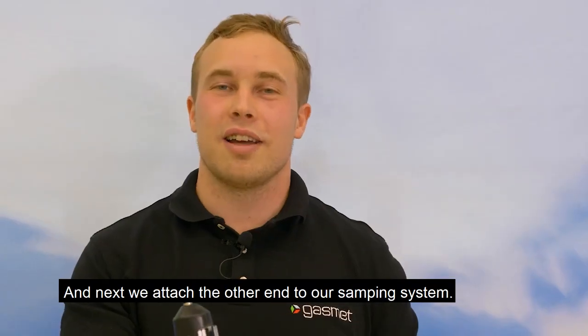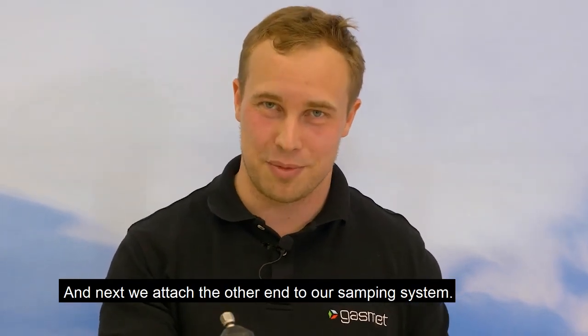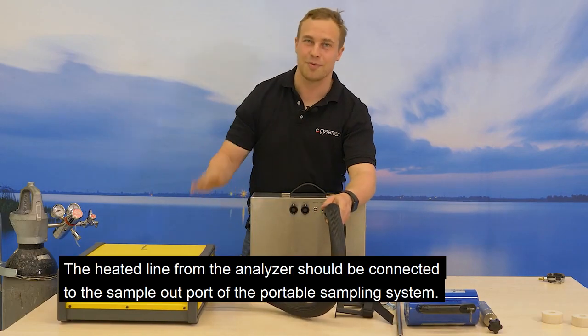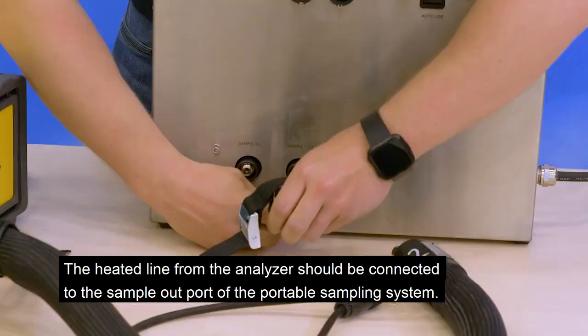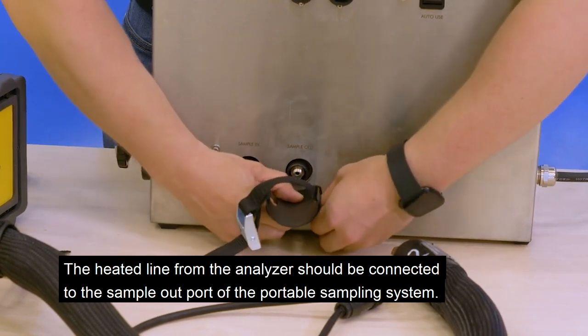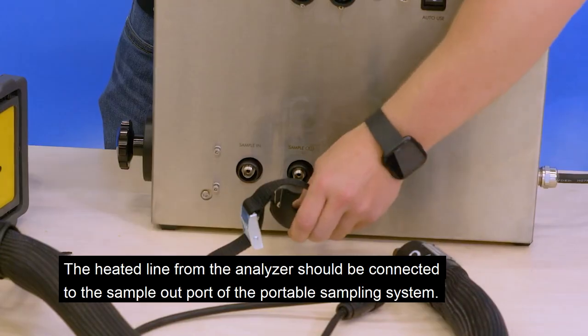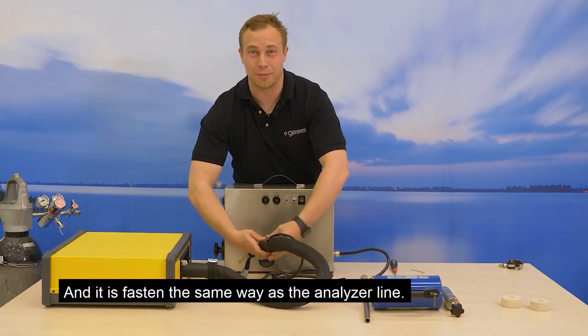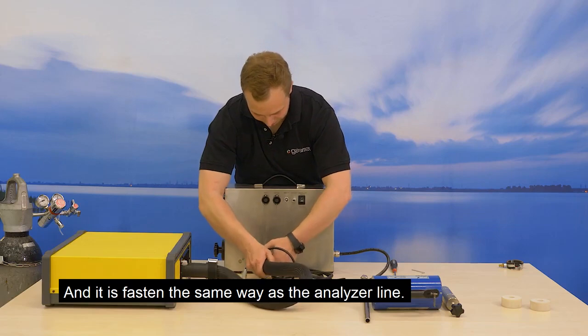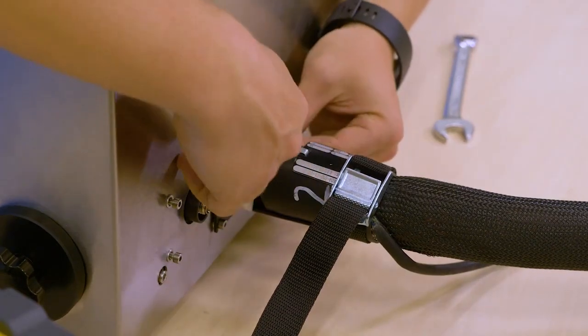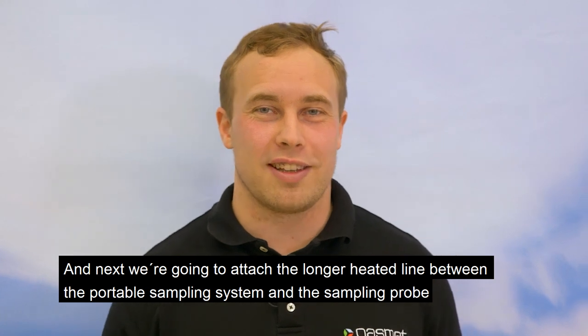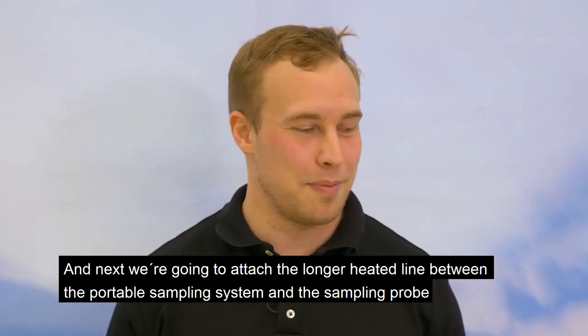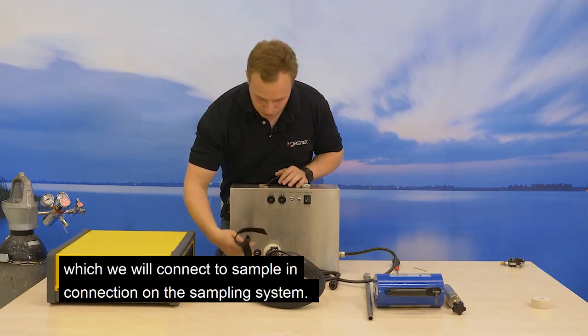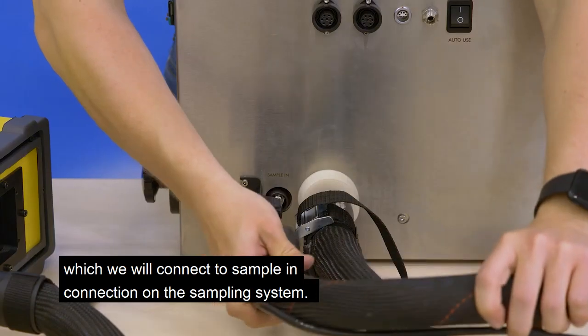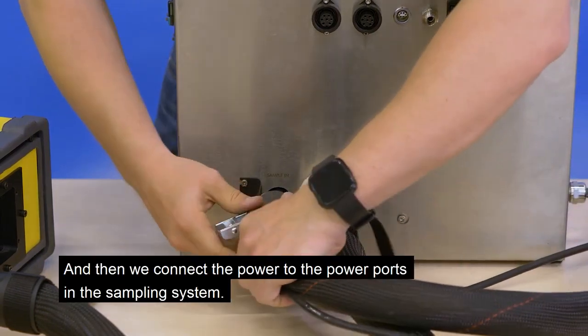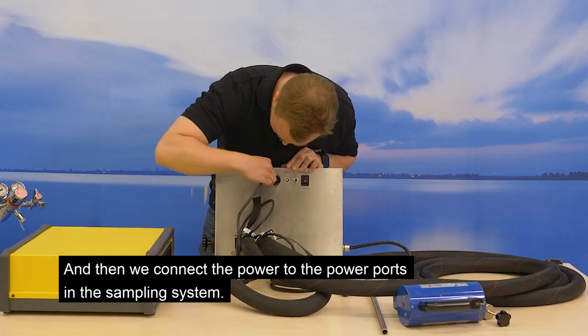And next we attach the other end to our sampling system. The heated line from the analyzer should be connected to the sample out port of the portable sampling system, and it is fastened the same way as the analyzer line. And next we're going to attach the longer heated line between the portable sampling system and the sampling probe, which we will connect to the sample in connection on the sampling system. And then we connect the power to the power ports in the sampling system.